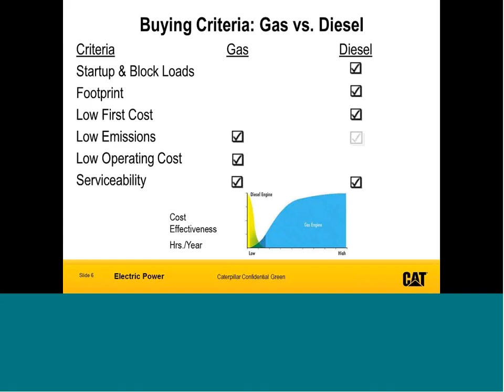What we're showing here on this chart is just your rental rate on a gas genset will be higher than a diesel genset, but if you look at the overall total cost, dollars per kilowatt hour, running any significant hours at all, you'll start to save some serious money on a gas genset. So gas is becoming more and more a preferred source of supply in reliable circumstances.